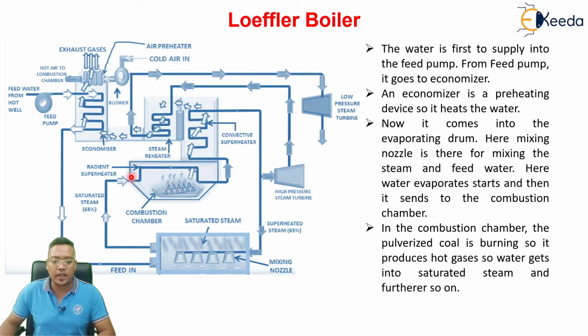After the combustion of the fuel, this saturated steam will convert into superheated steam and then it will go into the convective superheater. The steam coming from the convective superheater is superheated steam. Now 1/3 of the superheated steam will be sent to the turbine and 2/3 will be sent to the mixing chamber. The 1/3 steam will be sent to the high pressure turbine for the generation of power. After the expansion of this steam, it will be sent again into the boiler, into the reheater. After reheating, it will be sent to the low pressure turbine for the generation of power. So this is the steam and water cycle.